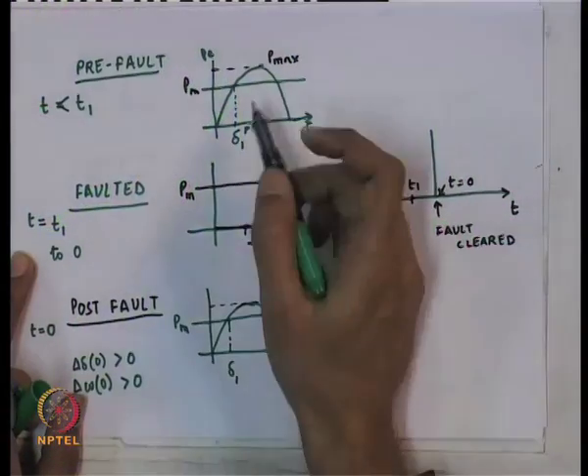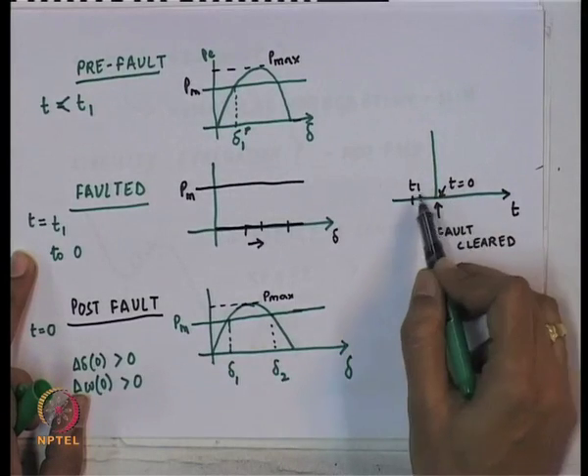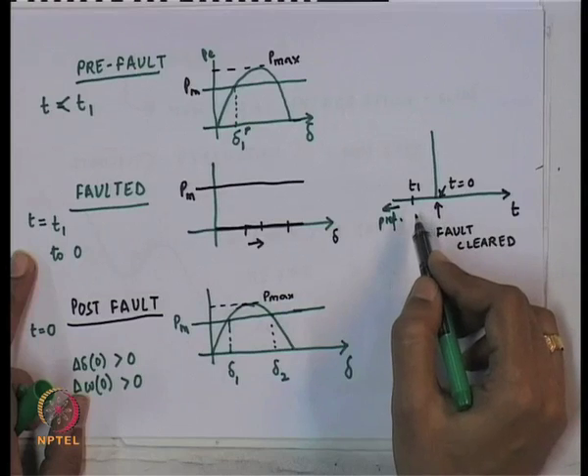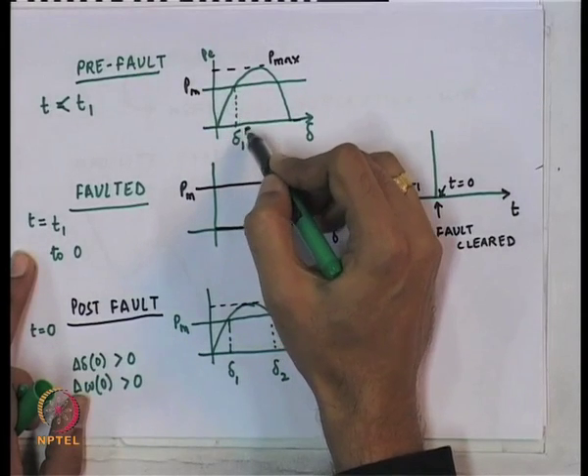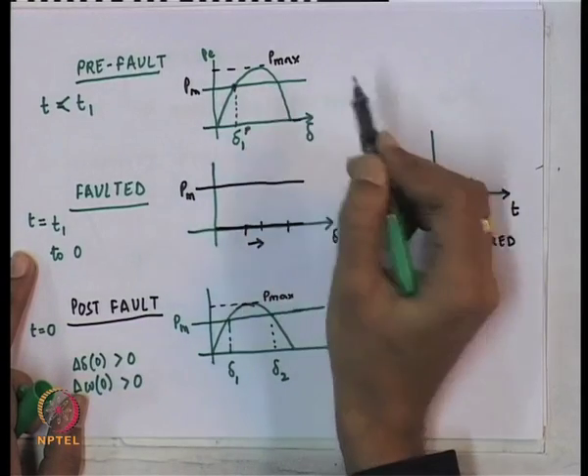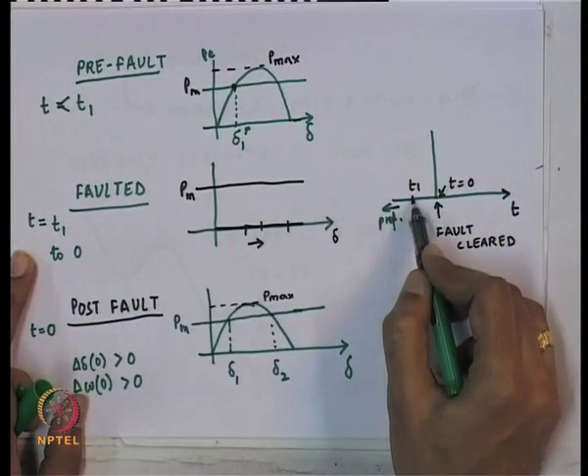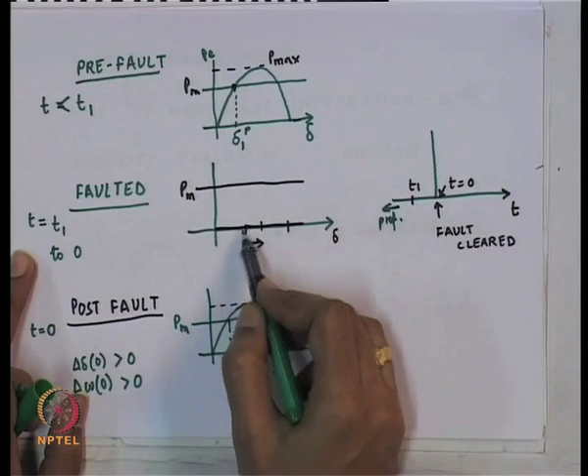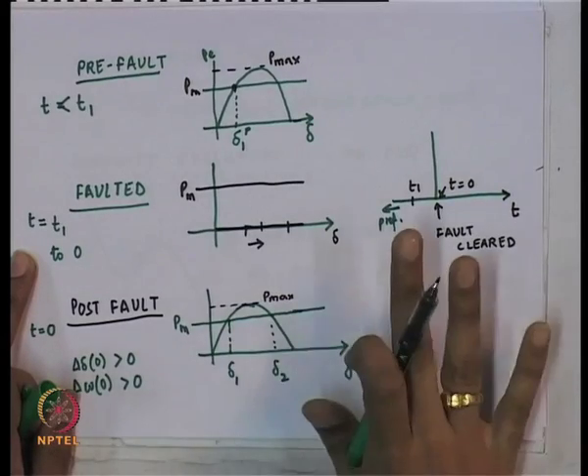Let us formulate this as a problem. Before time t_1, the system is in the pre-fault condition, operating at equilibrium delta_1 with superscript p. When a fault occurs at t_1, the electrical power becomes zero because the terminal voltage drops to zero for a three-phase fault. So the electrical power P_e becomes zero.